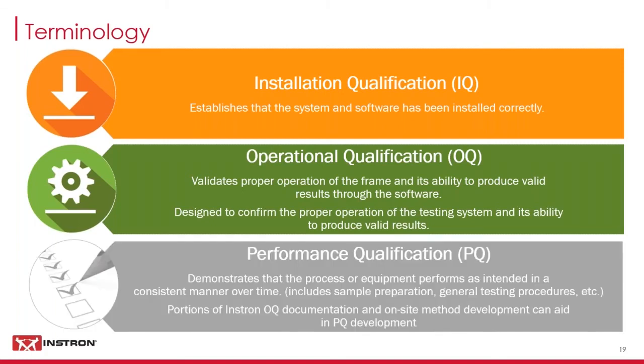Sometimes you may also hear IQOQ PQ instead of just IQOQ. What is PQ and why is it frequently left off? PQ, or Performance Qualification, demonstrates that the process or equipment performs as intended in a consistent manner over time. Because the PQ is specific to each customer, OEM vendors providing validation services for their equipment often offer IQ and OQ only. While most of the PQ is each individual customer's responsibility to document and implement, portions of Instron IQOQ documentation and on-site method development can aid in PQ development.